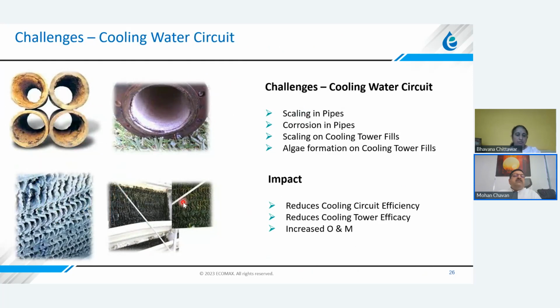When we look at the challenges that we have in the cooling water circuit, it is mainly corrosion, scaling in the pipes. Then we have scaling on the fills, algae formation on the fills. I mean, almost everywhere you'll have this kind of problems in the cooling towers. It could be severe, it could be less severe, depending on the water quality that is maintained. If you look at the impact of the scaling and algae formation on the cooling towers, it will reduce the cooling circuit efficiency overall. It also reduces the cooling tower efficacy. That means you don't get proper delta T. And it increases the cost of operations and maintenance, because then you have to clean the cooling towers frequently, you have to maintain, you have to replace the fills, etc.